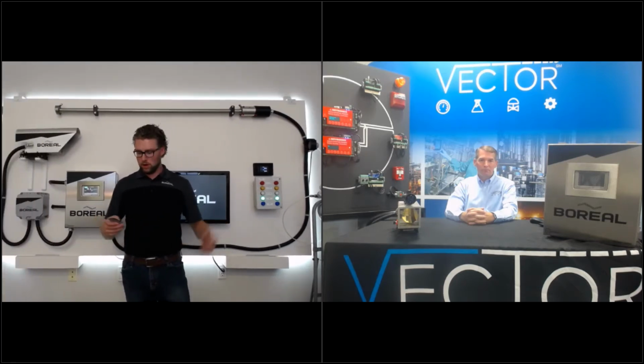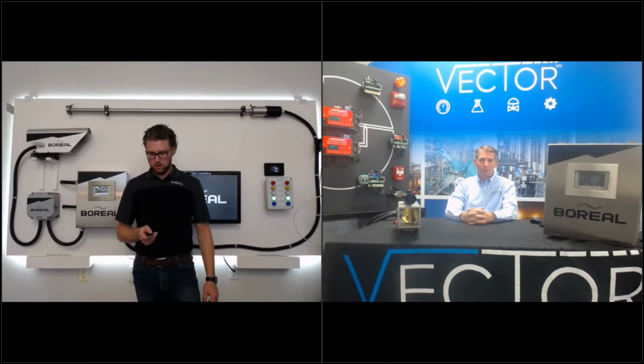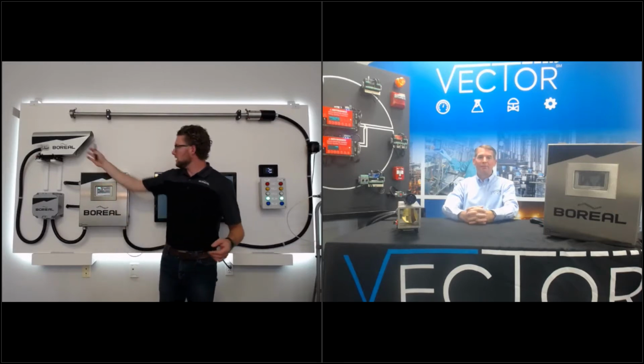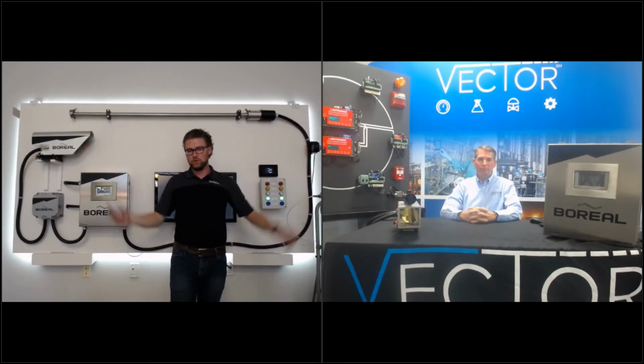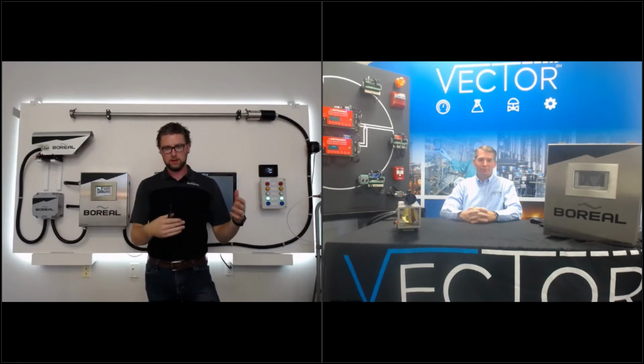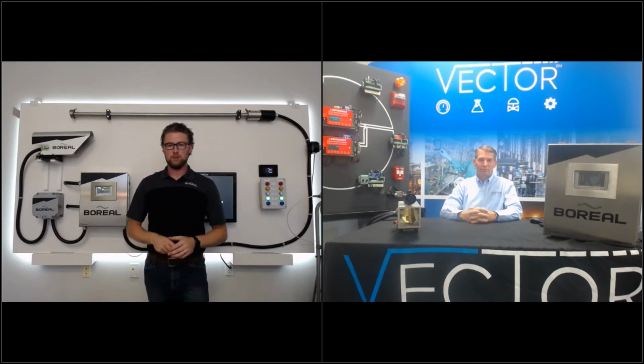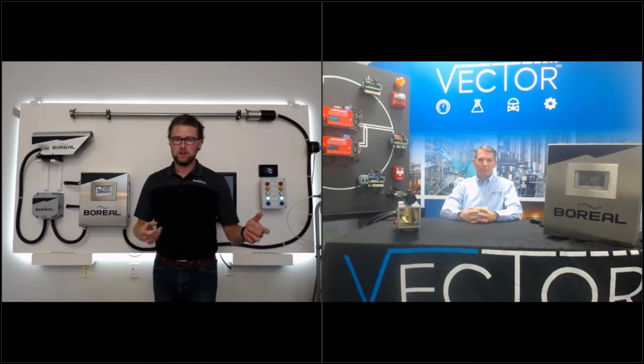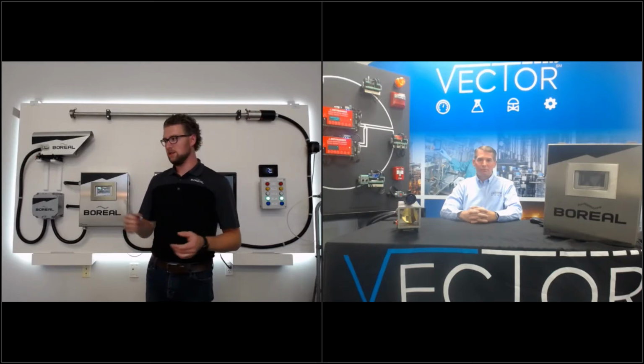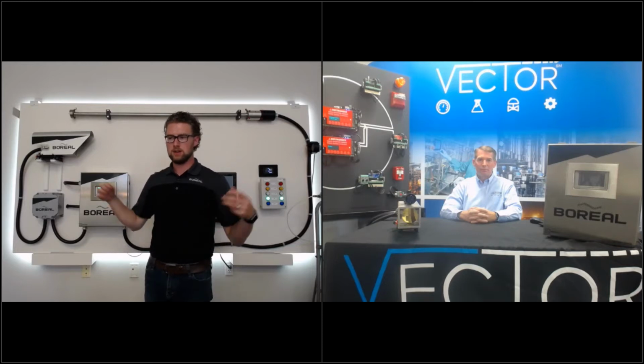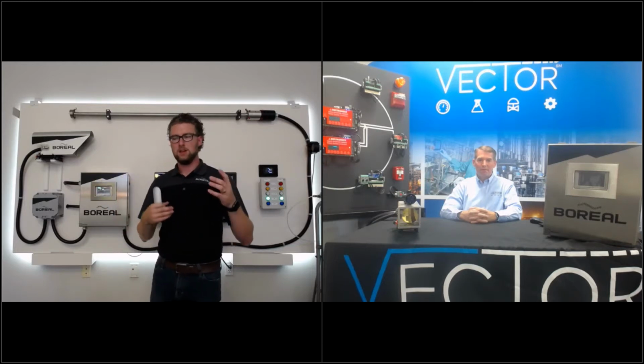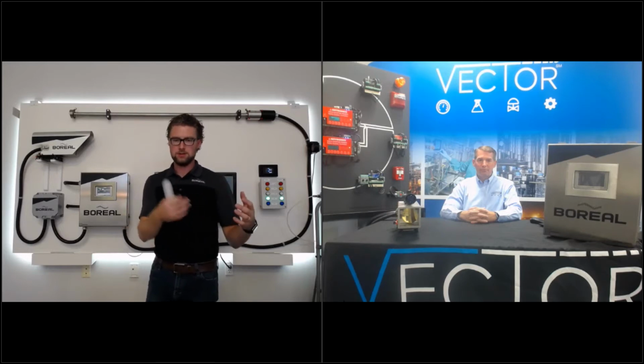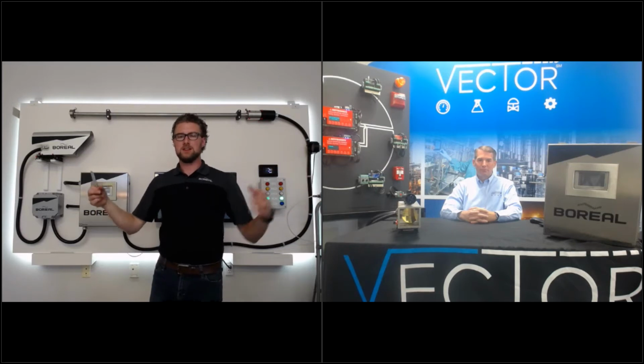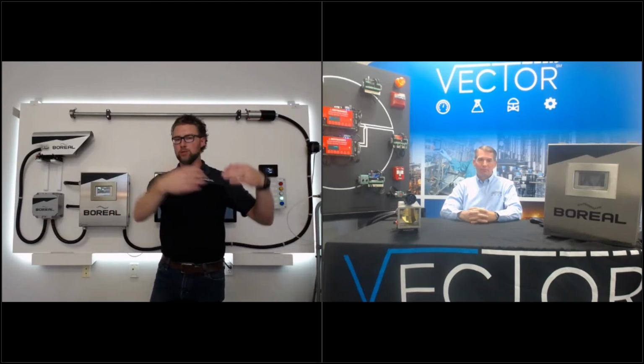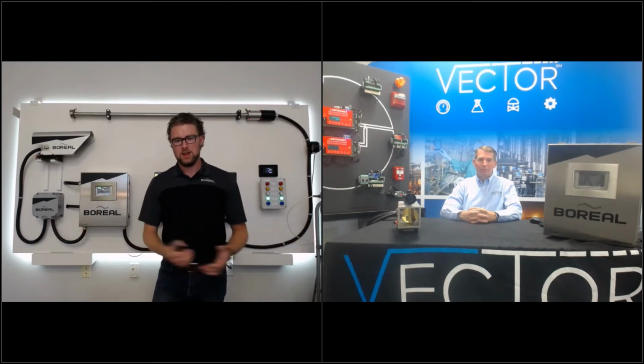Because we can monitor long path lengths, let me clarify what long path lengths are for these arrangements. Obviously, this is quite short. This active measurement path is just over 6 feet. So we can measure short path lengths like this, or we can measure very long path lengths. For example, up to 1,500 feet is our longest recommended path length. Our longest permanently installed path length is in the Middle East, measuring H2S, and that is well over 3,600 feet as well. So this technology is ideal for short path lengths in tight, congested process building applications. It is ideal for outdoor process areas, and it is ideal for perimeter or fence line monitoring around a process unit or an entire facility as well.